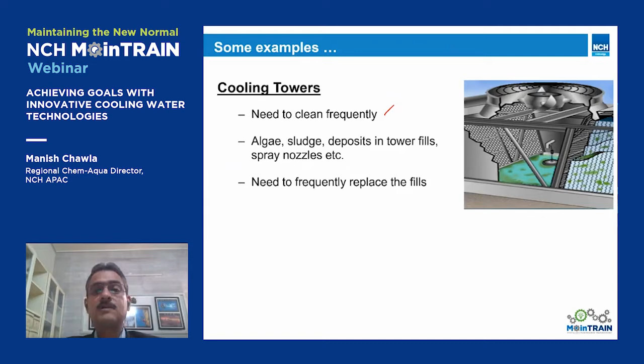For cooling towers, if you have to clean them very frequently, or find a lot of fouling matter in the spray nozzles, or algae and scale deposits inside the fills requiring replacement after 5 years instead of the expected 10 years, these are signs of the same problem.